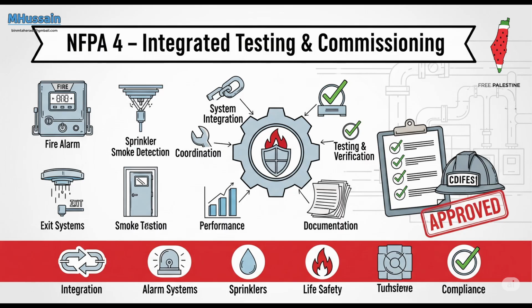And, related to changes, the standard is also quite clever about catching unintended consequences. How so? Let's say you modify one part of an integrated system. Maybe you upgrade the software for the smoke control system. Obviously, you test the known changes. But NFPA 4 also requires testing a sample of the unaffected input functions of systems that were changed. Wait, testing things that weren't supposed to be affected? Why? To catch those hidden domino effects. It requires testing typically 10% up to a maximum of 50 devices of the inputs that shouldn't have been affected by the change on each integrated system that was modified. So it's like a random spot check to make sure your software update for smoke control didn't accidentally stop the elevators from recalling correctly. Precisely. It's a safeguard against those subtle, potentially catastrophic ripple effects that you might not expect, making sure a seemingly small tweak doesn't disrupt other critical functions. That's a really smart proactive failure finding.